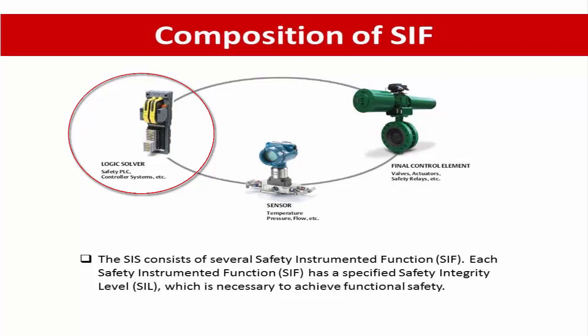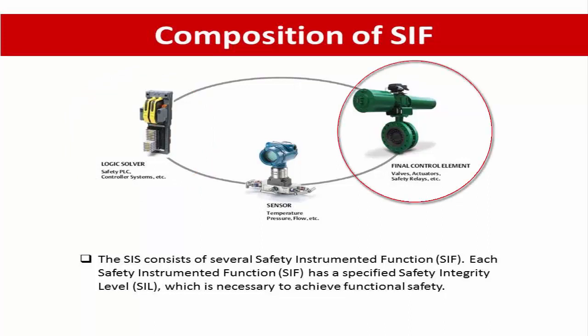Logic solvers can be programmable or non-programmable devices, and can also be mechanical in the form of a switch set to trip the function. The third element is the final element, which implements the action determined by the logic solver. Final elements are typically automated on-off valves with a fail-closed or fail-open function.